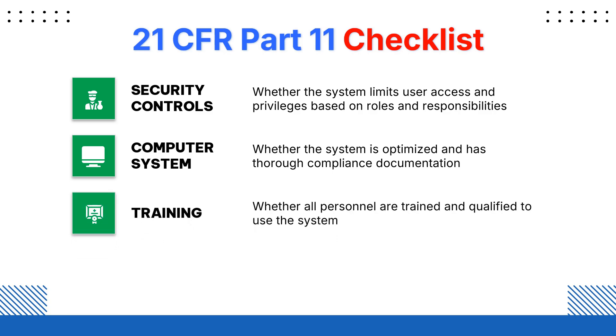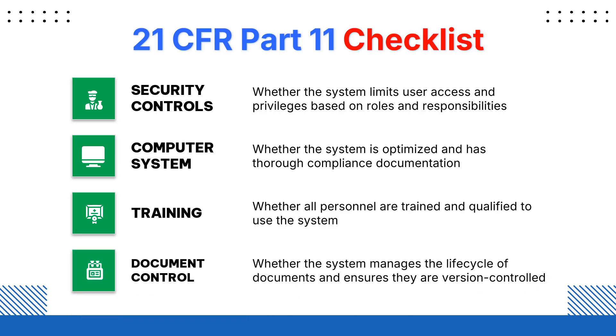Next is training. Whoever is using the system that is compliant to 21 CFR Part 11 needs to be properly trained and qualified to use that system — only then can we ensure that the data is not tampered with and is correctly maintained and entered. The last aspect is document control: whenever a system manages a document, the lifecycle of the document should be ensured, and we need to know whether the document was amended or there was a change in version, so version control needs to be in place.